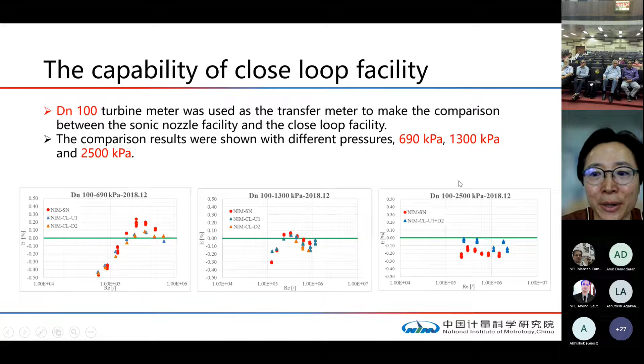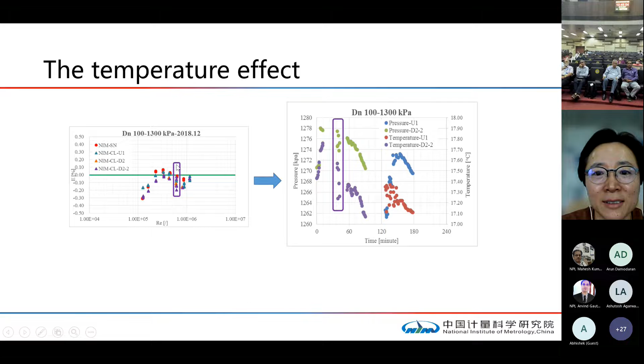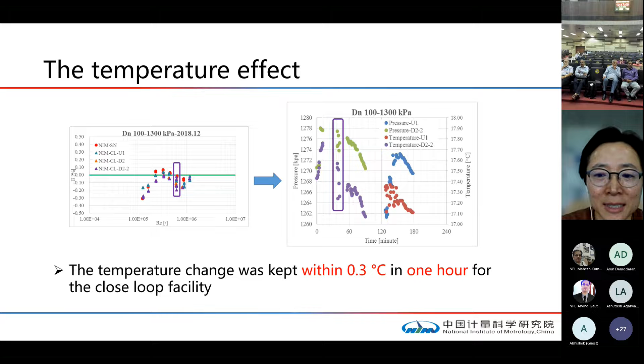Besides the turbine meter calibration, another challenge for the closed loop facilities is temperature control. You can see that for this calibration, the results are relatively scattered. The reason is the temperature control. After about 2 years of operation of our closed loop facilities, currently the temperature change can be kept within 0.3 degrees C in 1 hour.